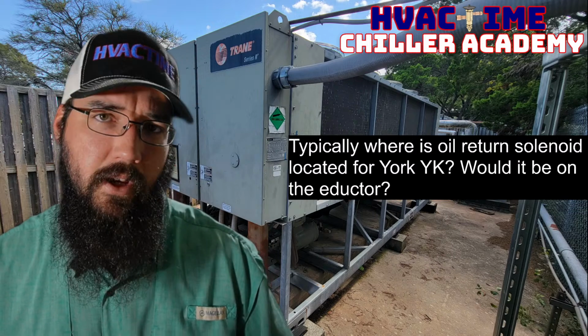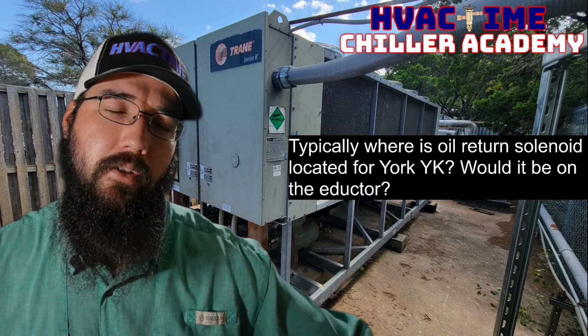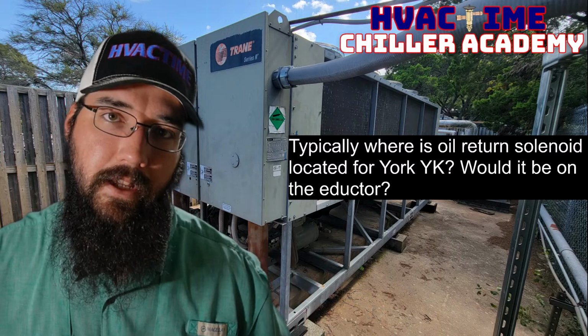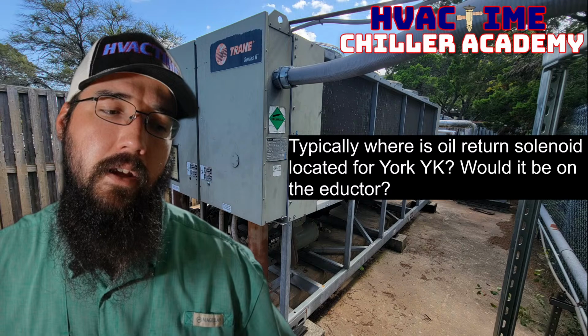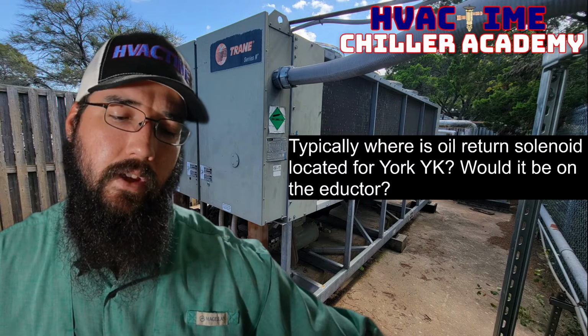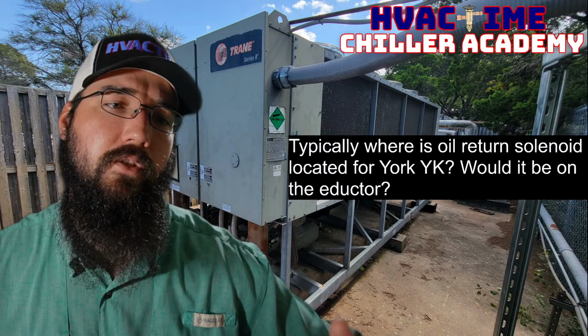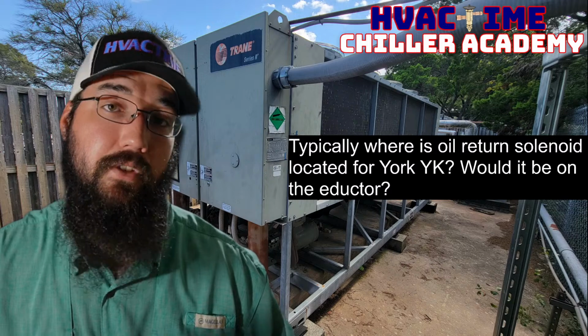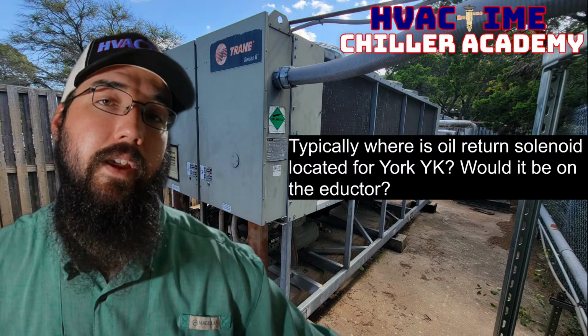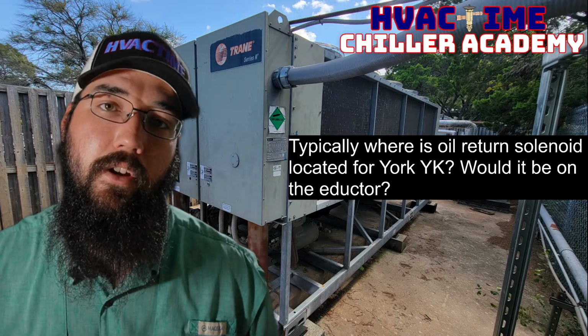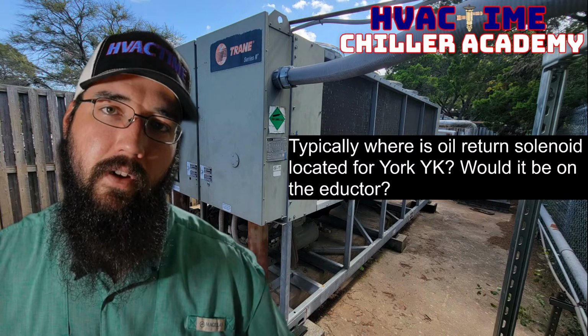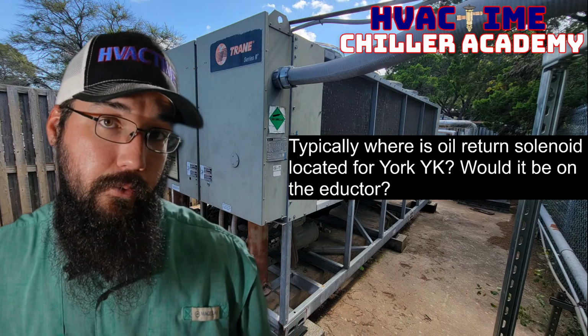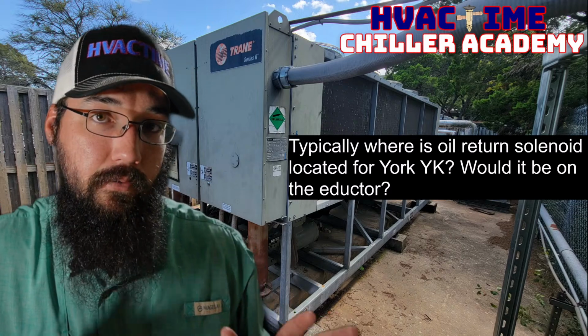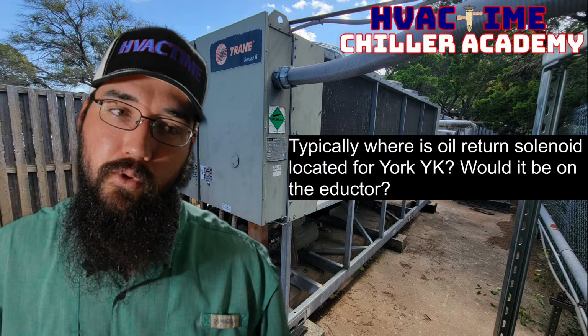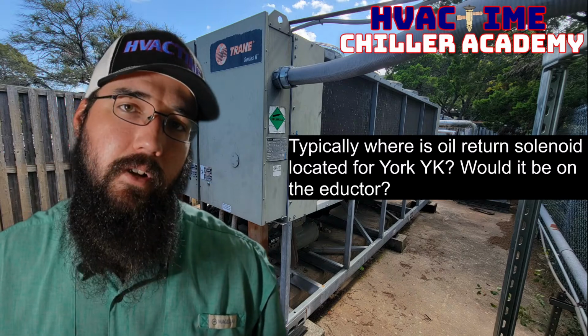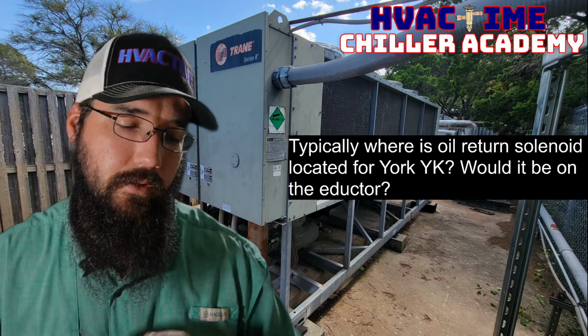There was a time when, especially in these older machines, when the metering or the variable orifice valve was first getting implemented, when they were transitioning away from the orifice plates for the original YKs, that it was just common practice that, you know what, those metering valves, the PID for them just had too many issues. We're just going to remove that because it's just creating a problem, and they would manually open that valve, or they would adjust the set points to where the valve would basically just stay open all the time. What that would do, though, and many times it would cause, especially if you do that on a newer machine, which has significantly improved since the early versions, you'll see that evaporator level just run way too high. You'll run hardly anything on the condenser. It causes all kinds of problems there.